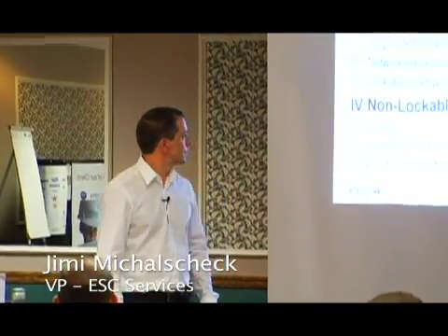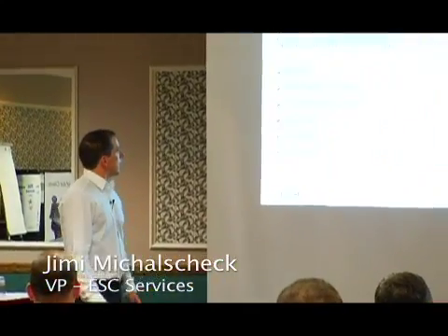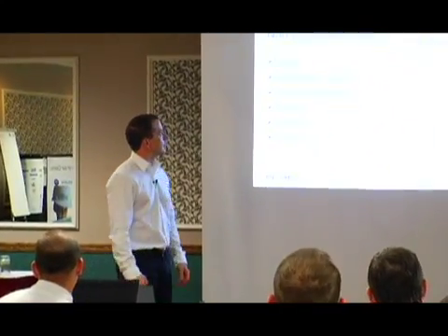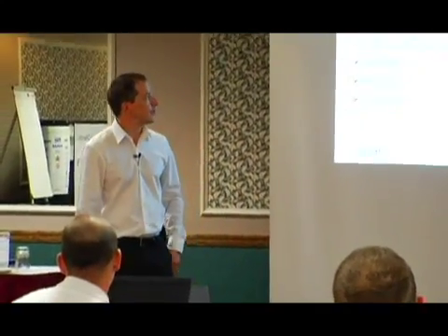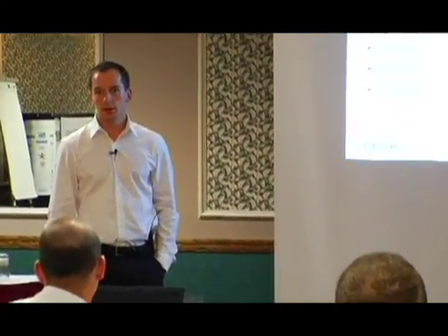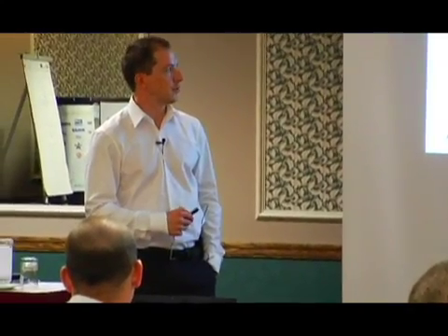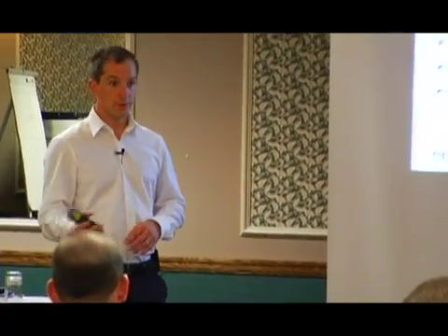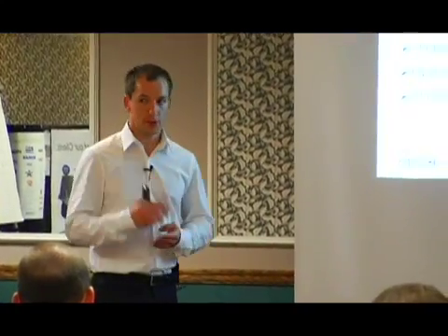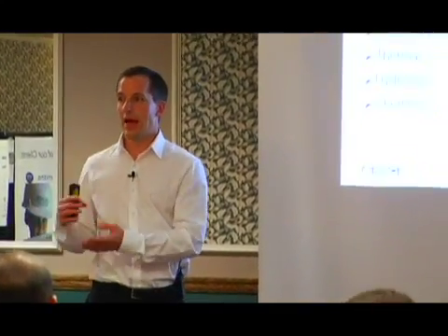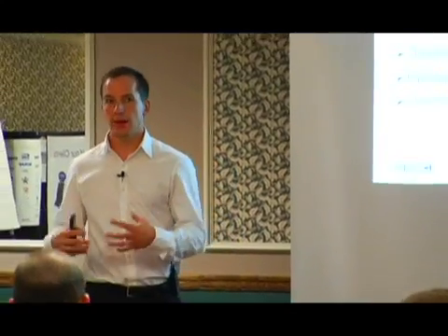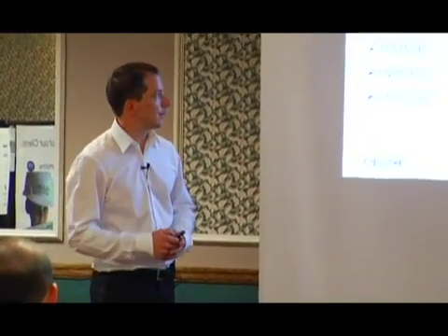So now we're going to look at non-lockable energy sources. Kinetic, anything moving. Potential from gravity, potential from springs. Also, there can be a potential from capacitors inside a machine. Most capacitors in modern equipment will self-discharge over a period of time. Older equipment, you really need to understand if there's a capacitor in there, how to discharge it, how to safely bring that capacitor to zero energy state.